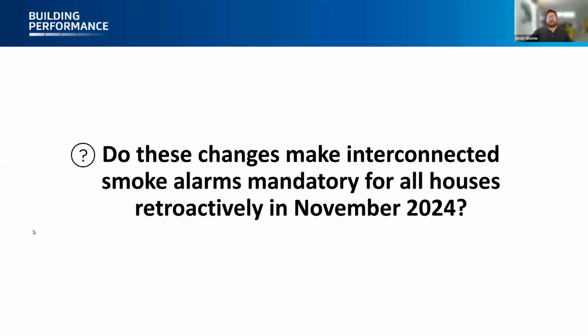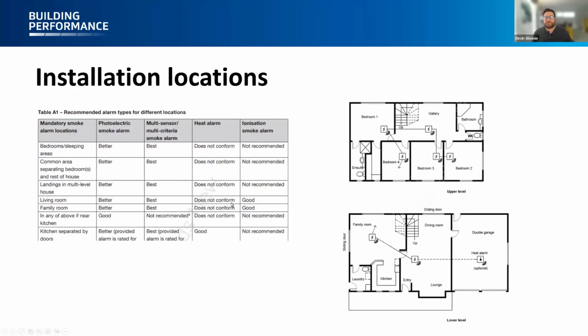Some of the installation locations are covered in the standard. If they're required throughout a house, will you get a lot of false alarms? These are the diagrams you can find in the standard. For instance, the garage is a bad place to put a smoke alarm, because car exhaust or even dust might set off the alarm. So the recommendation is to put a heat detector or heat alarm in the garage instead of a smoke alarm.